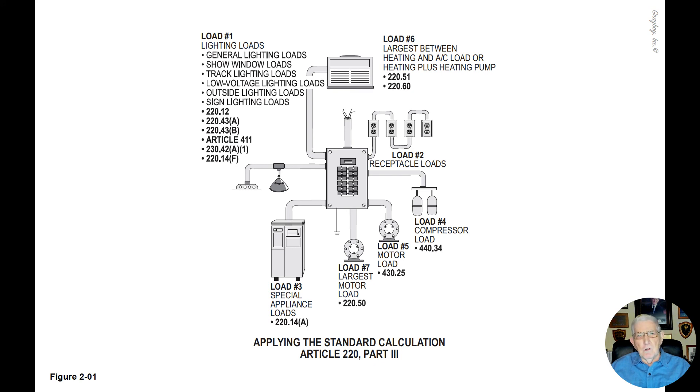If your load is not listed in that table, then you know it's usually considered you can't size that overcurrent device greater than 125 percent of the load to size your conductors and the overcurrent device to supply power to these loads.